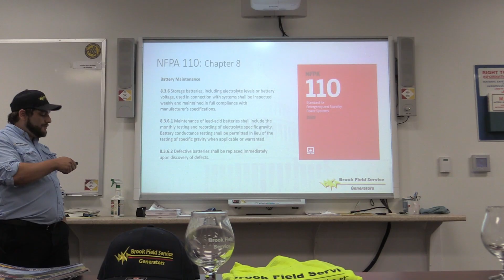The other thing is, manufacturer's best practice is that batteries should be replaced every 3 years. And I know we get a lot of resistance from clients on this. They say, well, you test the battery, it's fine. But the manufacturers are recommending it, which is what NFPA 110 says, whatever the manufacturer recommends, and for batteries that's every 3 years. So if you think someone's trying to sell you a battery unnecessarily, that's really not the case. It's just because these systems are considered legally required.